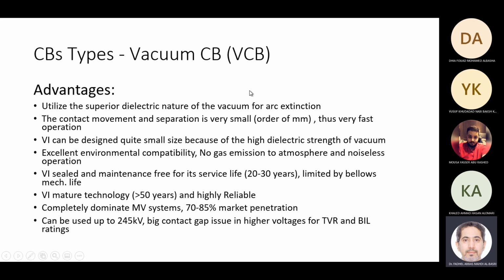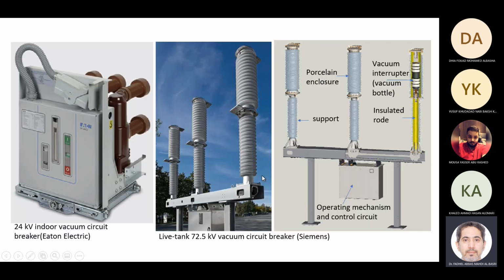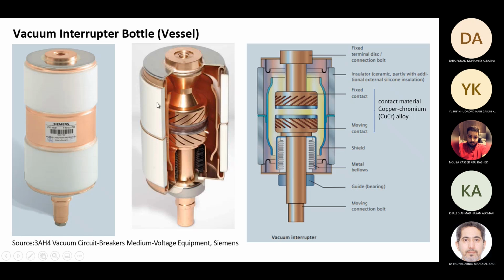The vacuum interrupter is like a tube, and I'll show you a figure now. This is a vacuum tube. Okay, these are the contacts. One is fixed, one is moving. The lower one is moving, and it's made of an alloy, like copper plus, let's say, chromium. This is the bellows. It's like a spring that helps to close and open the moving contact, and it is fully sealed. So here it will be under vacuum, so the arc will be under vacuum. This will be sealed for lifetime.